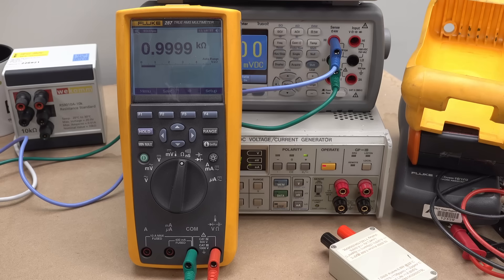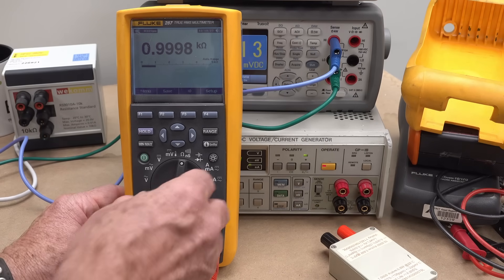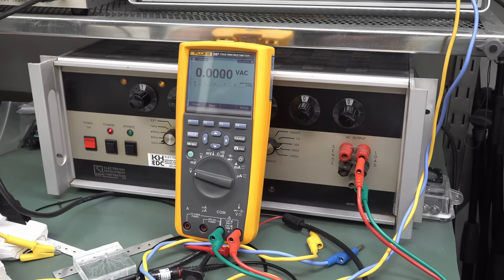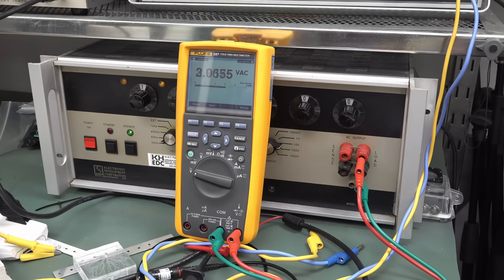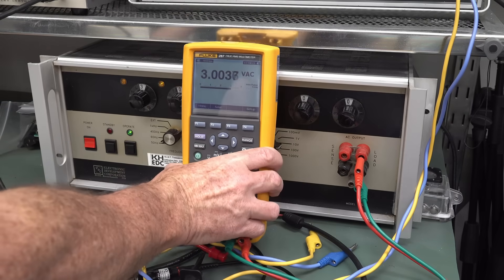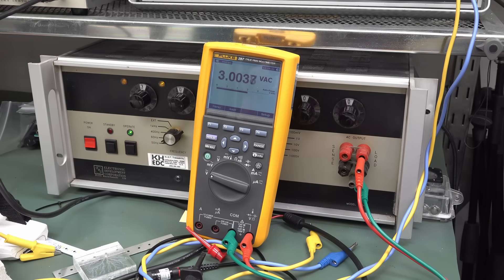I'm sure the AC is fine too. Yeah, let me try the calibrator. Here we go. I've got it set to three volts AC. So let's operate that. It'll take a second to settle down. But once it's settled down, it locks in and bam, that's as close to bang on as you're gonna get. They're all set to zeros on there. But I haven't warmed this AC calibrator up. It's just turned it straight on and operate. And basically, that is bang on. And that's well within spec anyway. The AC specs usually on a good meter like this, like 0.2% or something. So yeah, that's gonna be good enough.